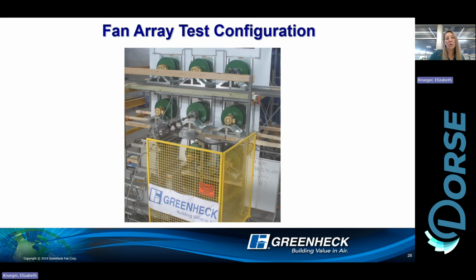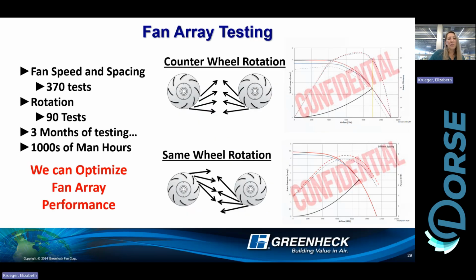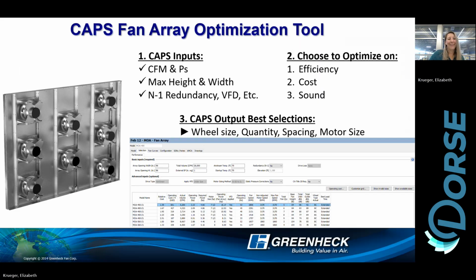As they did one test, they kept moving the fans farther and farther apart, and we were able to test the airflow as they continued changing the spacing on them. So that means with these tests, we tried different rotations, counter rotation, same rotation. Apparently it took 3 months of testing. This was a little bit before I actually joined Greenheck, but they got some excellent results. And those results now resulted in our optimization tool for our MOA.